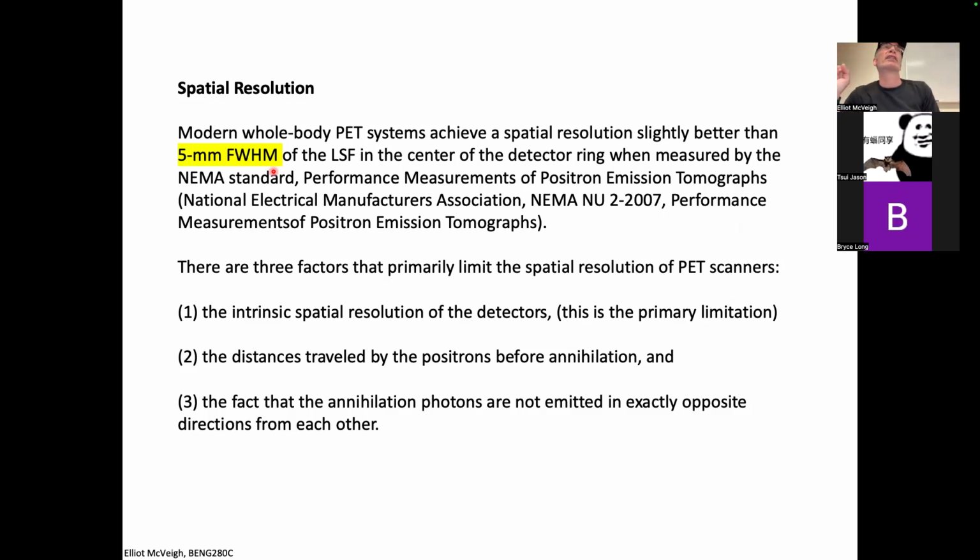That's what I'm going to see for that object. And so you convolve everything that is the ground truth, where all of these positron emitters are, with this 3D Gaussian, right? And that's your spatial resolution of a PET scanner, which is pretty good because for SPECT, it's about 10. This is like twice the blurring in SPECT.